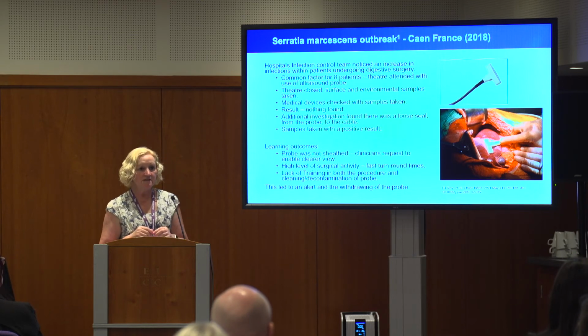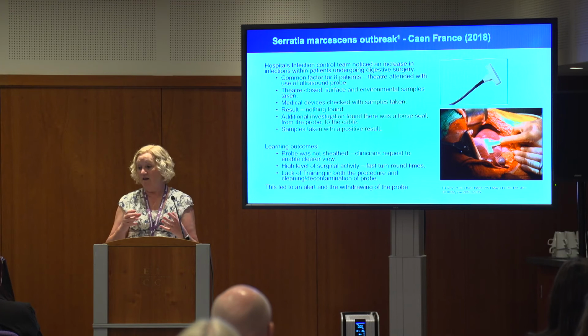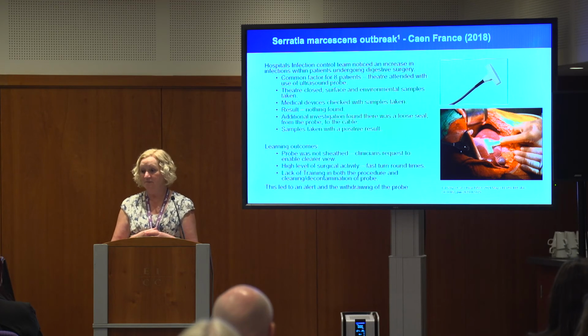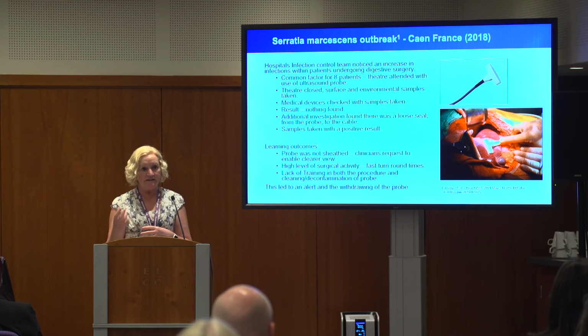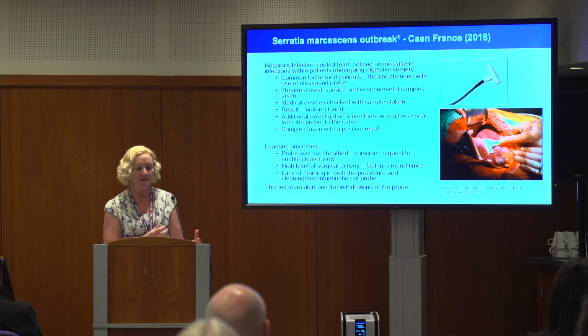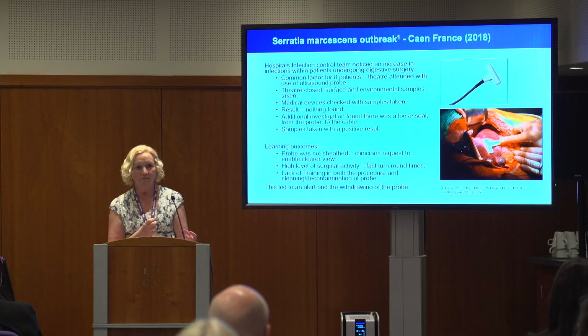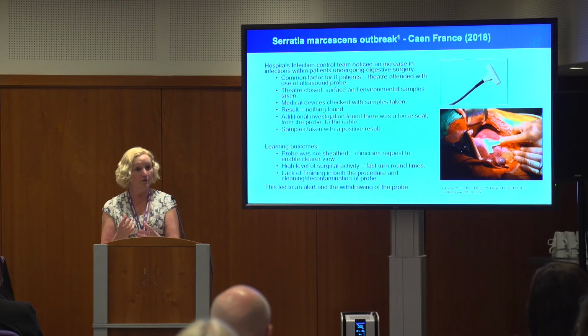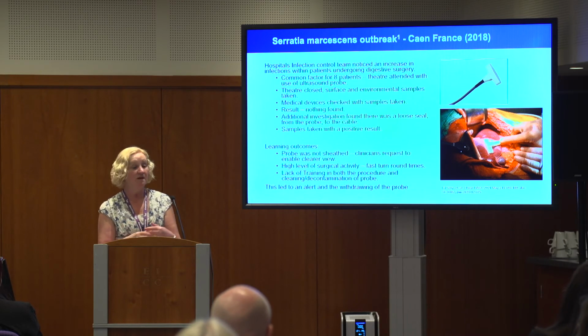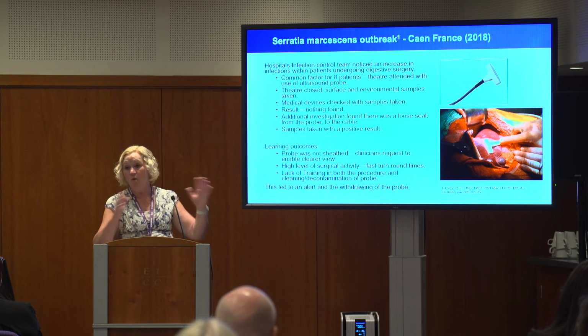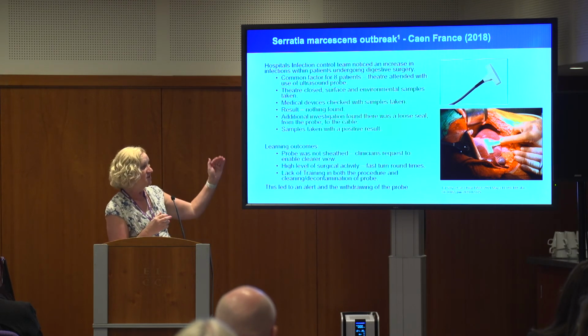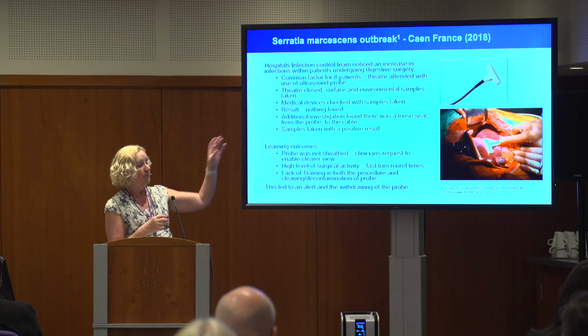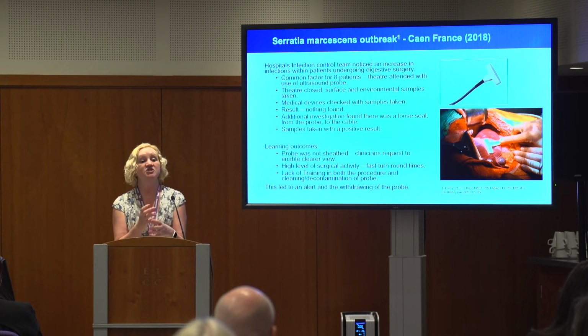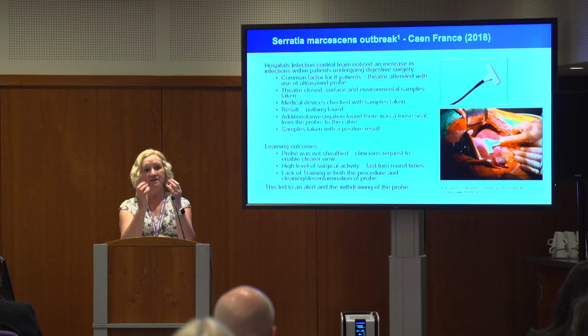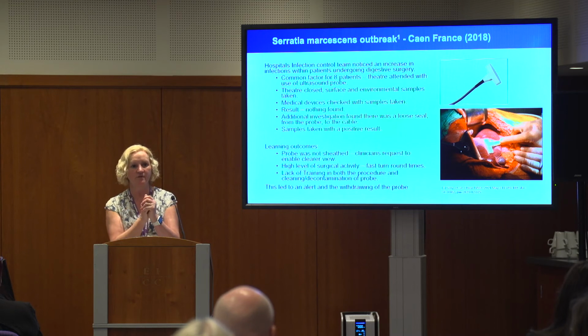There was a more recent incident in Caen, France where a liver resection was taking place and subsequent patients got infections. It was due to inappropriate cleaning of the probe, but it was due to them being busy, a lot of turnover, staff not being trained, the ultrasound probe actually having a problem with it, but no one recognising that there was a problem. So they closed the theatre, they swabbed everything, they didn't find a problem. When they came to look at it, they discovered that when they immersed the probe into water, they got contamination and they were able to get growth from it. And one of the little seals had gone, and contamination had gone down through there.